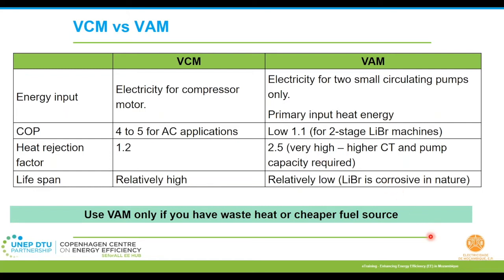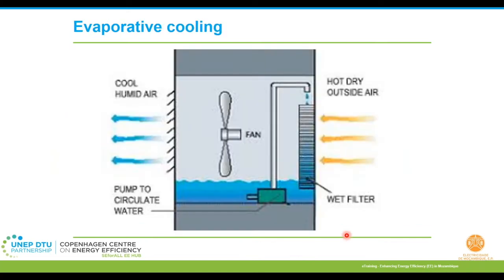In short, it is generally recommended by most people that you use VAM only when you have some source of waste heat or a cheaper fuel source, or else it is generally not recommended. The third part is evaporative cooling, where air is brought into close contact with water to cool it to a temperature close to the wet bulb temperature. It is mostly used on shop floors and in comfortable climate zones, and in dry regions, where you don't have any refrigerant or compressors involved. It's just heat exchange between water and air.